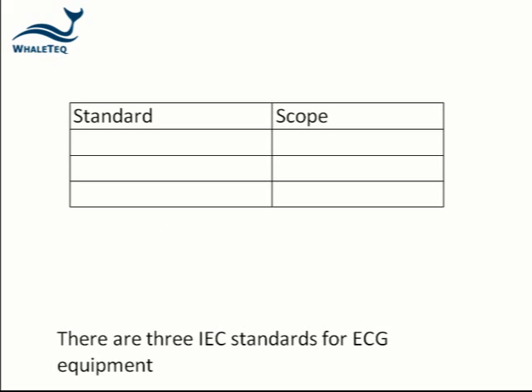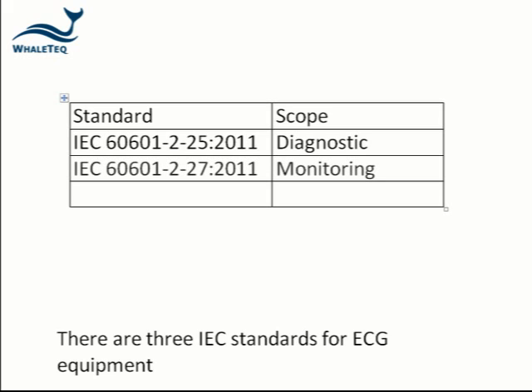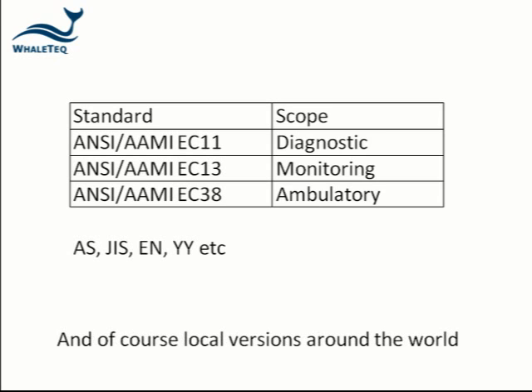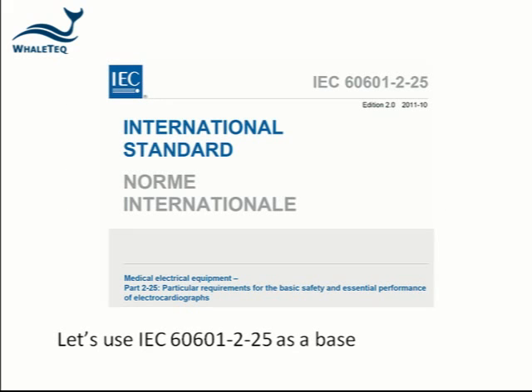There are three IEC standards for ECG equipment: IEC 60601-2-25 for diagnostic, 2-27 for monitoring, and 2-47 for ambulatory or Holter ECGs. In the US there are similar standards, and of course a range of standards around the world for national regulations. For now let's use 2-25 as a base for the tests and discuss the variations later on.